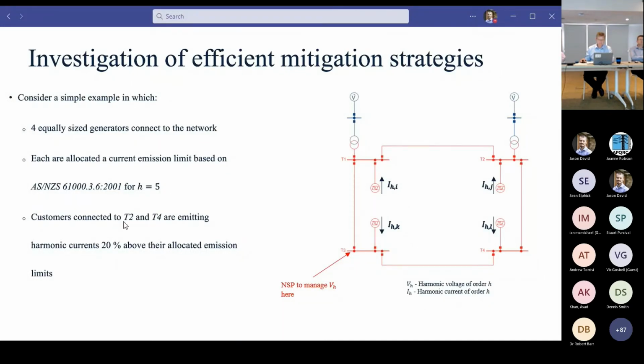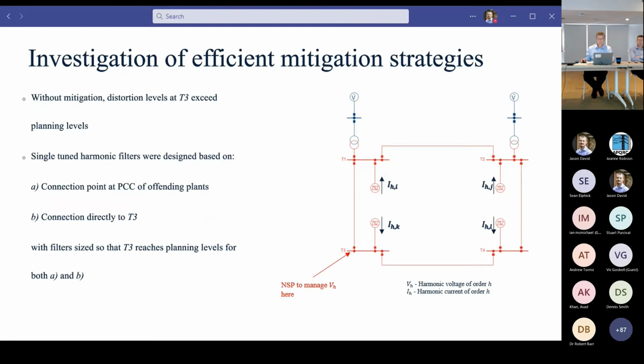And what we find through modeling is that customers connected to terminals 2 and 4 are emitting harmonic currents that are 20% above their allocated emission limit. So in this case, we can expect that our planning levels are going to be exceeded here at T3, terminal 3. So some level of mitigation is going to be required.